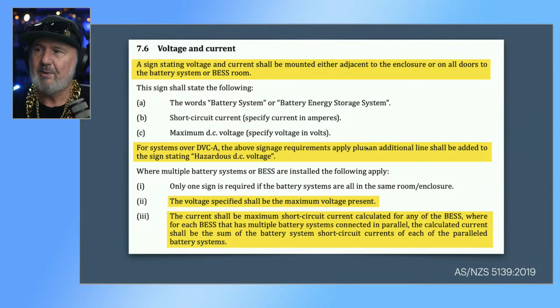The current shall be the maximum short circuit current calculated for any of the BESS, and where each BESS has a multiple battery system connected in parallel, the calculated current shall be the sum of the battery system short circuit current of each of the paralleled systems. So in my case, with 40 battery modules in parallel, I've got to sum the fault currents of all 40 of them to get the maximum prospective fault current. And so I approached the manufacturer to find that out.